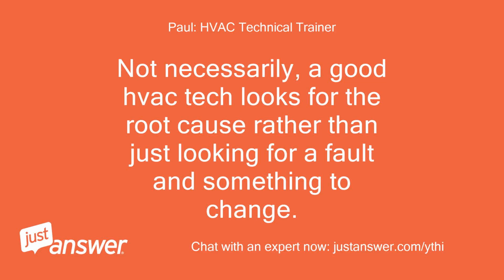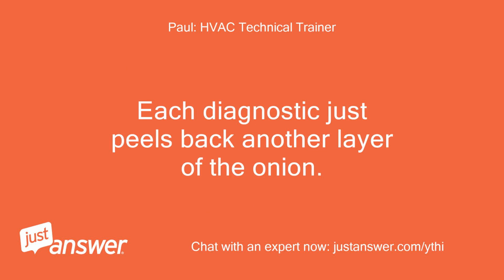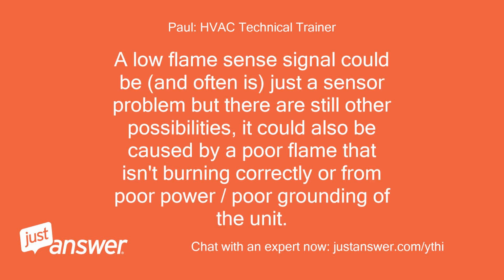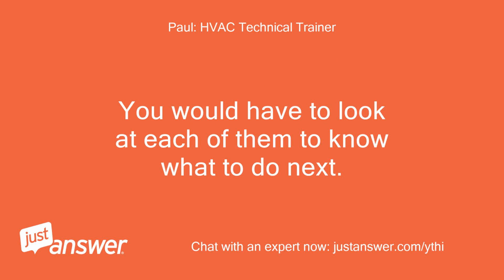Not necessarily. A good HVAC tech looks for the root cause rather than just looking for a fault and something to change. Each diagnostic just peels back another layer of the onion. A low flame sense signal could be, and often is, just a sensor problem, but there are still other possibilities. It could also be caused by a poor flame that isn't burning correctly or from poor power, poor grounding of the unit. You would have to look at each of them to know what to do next.